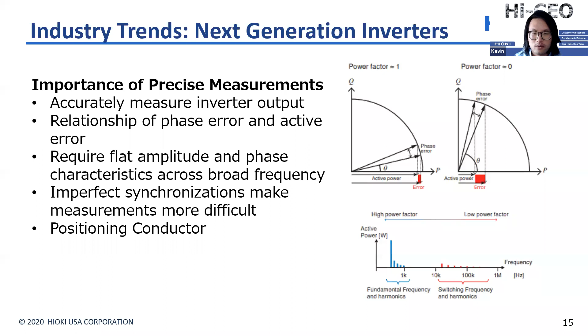And because these current sensors work by detecting the magnetic field produced when the current flows through our cables, we need to make sure that we keep any conductors away from the sensors if possible, since the effects will be more significant at the higher frequency currents.